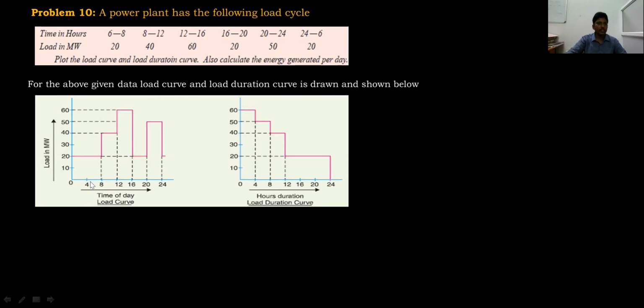So we have drawn the load curve, and from here we can find the maximum demand. The question also asks for the load duration curve to be drawn. For the load duration curve, first we have to draw the maximum demand. Maximum demand on the power station is 60 megawatts, for how many hours? 12 to 16 means 4 hours. So from 0 to 4 hours, the maximum demand is 60. Next is the next highest peak, which is this one.